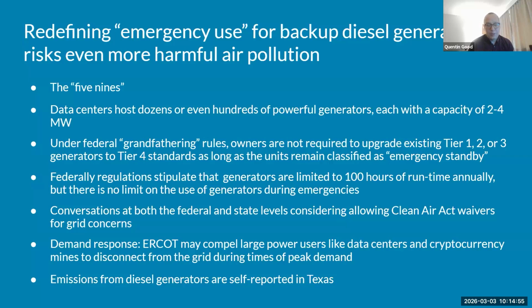However, there's no runtime limit if it can be defined as an emergency under federal standards. In some cases, they can get temporary permits to run above the limitation. In Texas, this could happen if data centers or crypto mines are asked or compelled to participate in demand response programs when the grid is stressed, reducing their grid load but shifting power to diesel generators without run-hour limits.